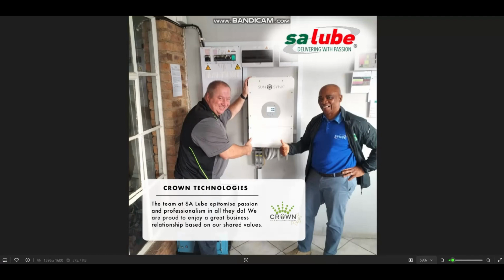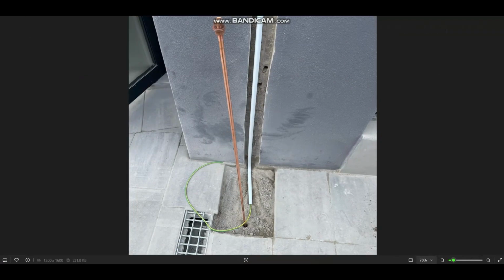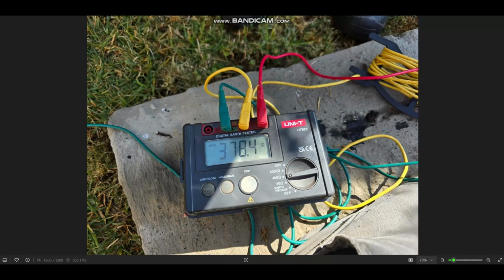The fourth layer of surge protection, possibly the most important one, is your earthing system. So this is for when, not if, but when your panels sustain a direct lightning strike, they must earth on their own earthing system. This is a photograph of one of the copper and galv spikes, and there you can see is the line going directly up to the array. Now, it's important to note that you can't just put one spike in and think everything's going to be fine. You need to quantify the resistance of that earthing system, and it needs to exhibit less than 20.